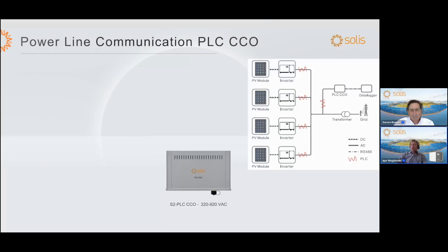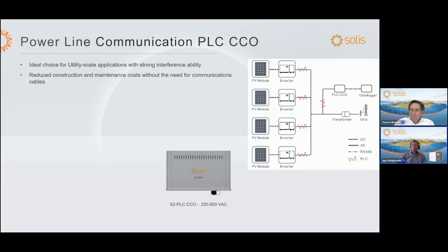This shows the PLC communication. Basically you have one communication device per skid or per installation. It has advantages for utility scale applications because the communication is done through the power line and no copper wires are required. That also prevents lightning issues and other issues that could damage the communication devices in the field. It reduces construction costs and cables. It's rated 220 to 920 volt AC, so an 800 volt device can be easily connected with the PLC communication. Up to 80 devices can be connected to a single PLC device.